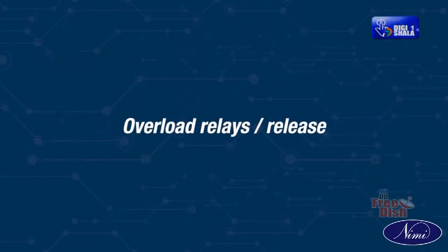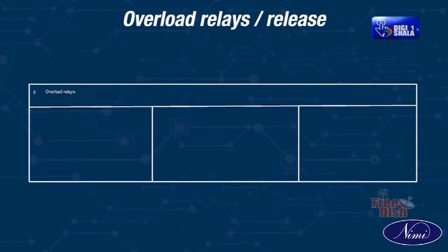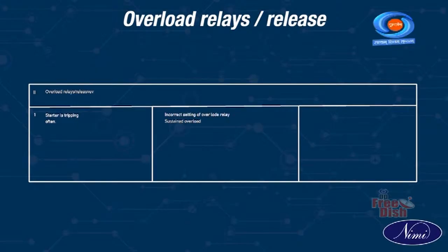Overload relay or release. 1. Starter is tripping often. Incorrect setting of overload relay, sustained overload. Reset properly. Check for faults, excessive motor currents.